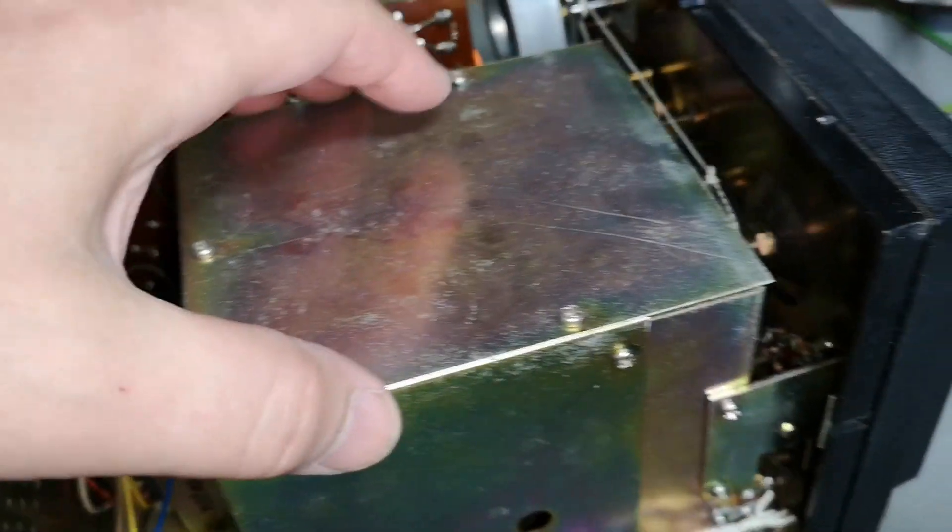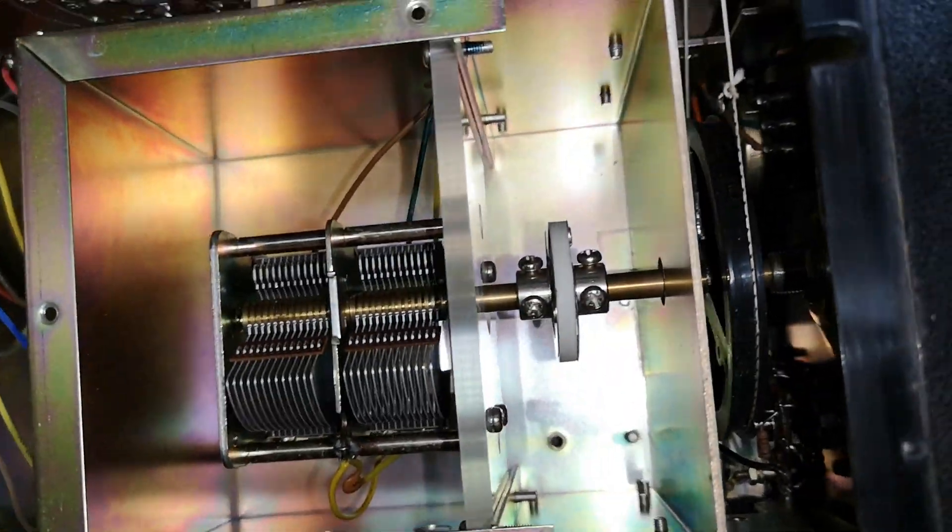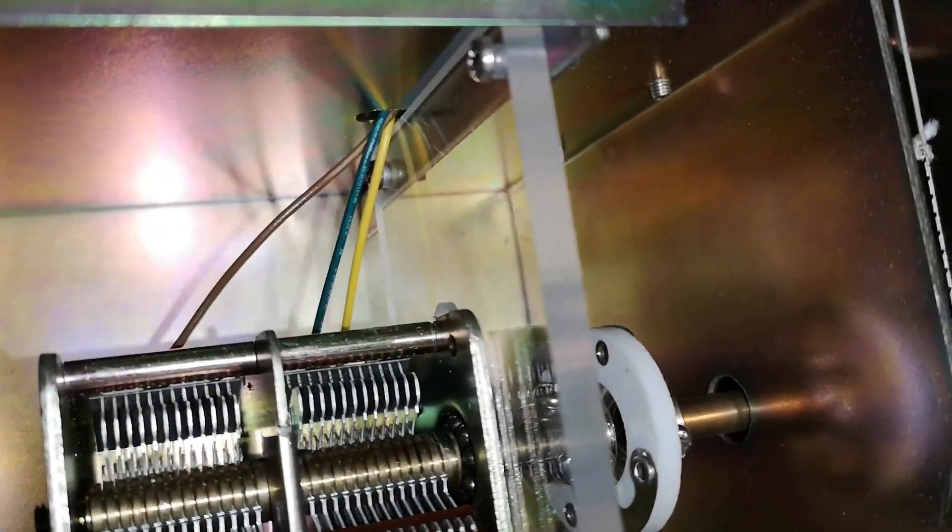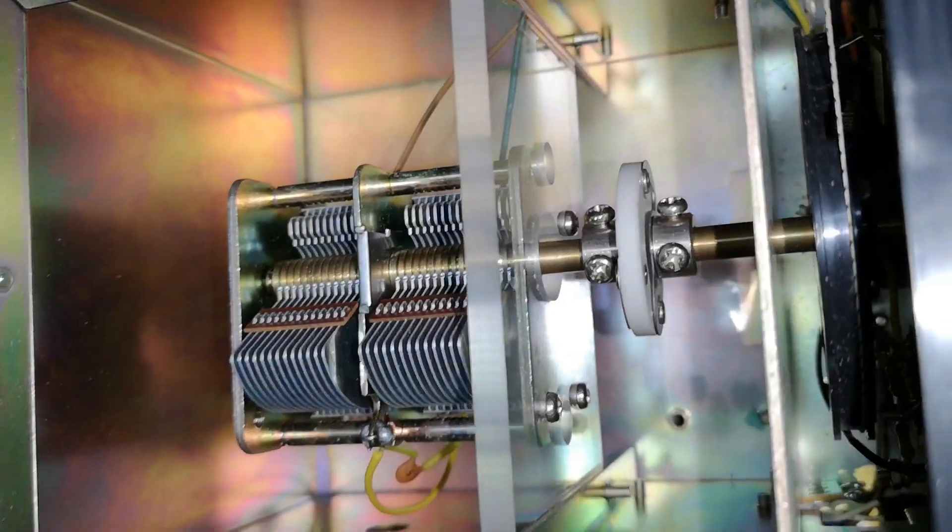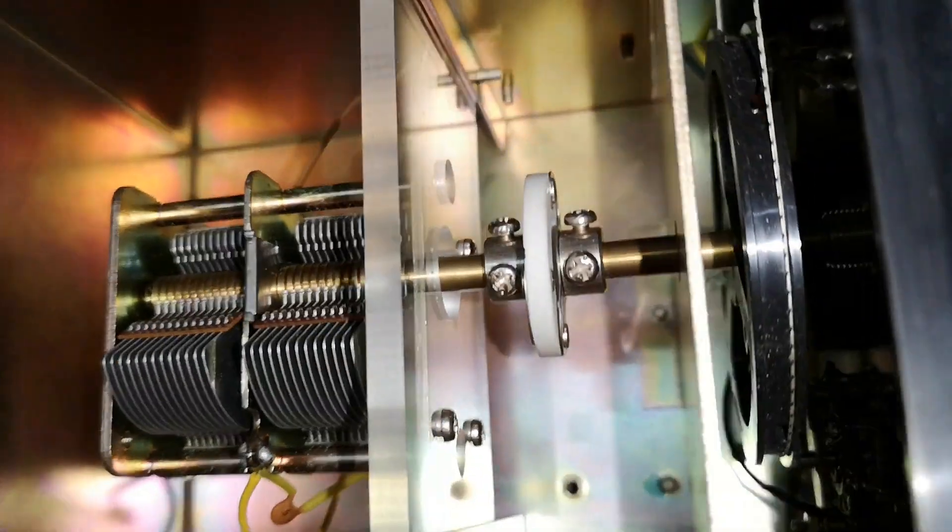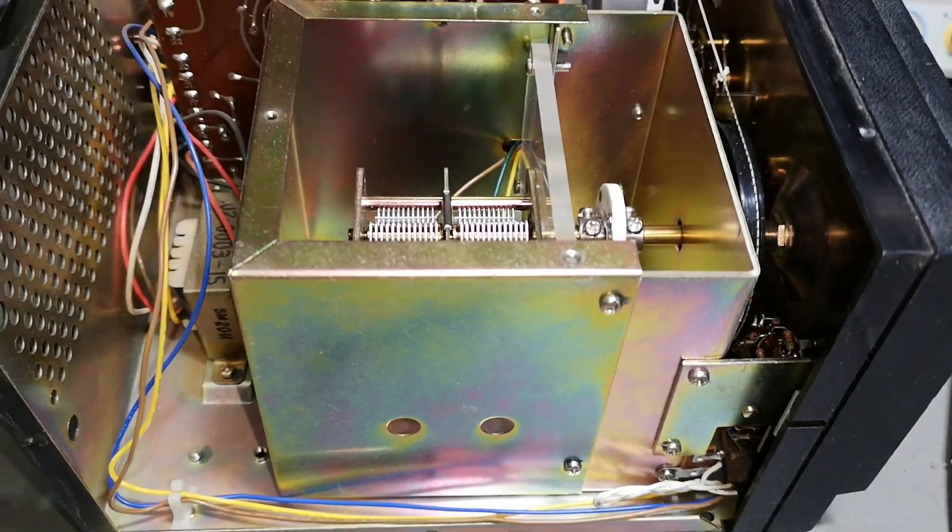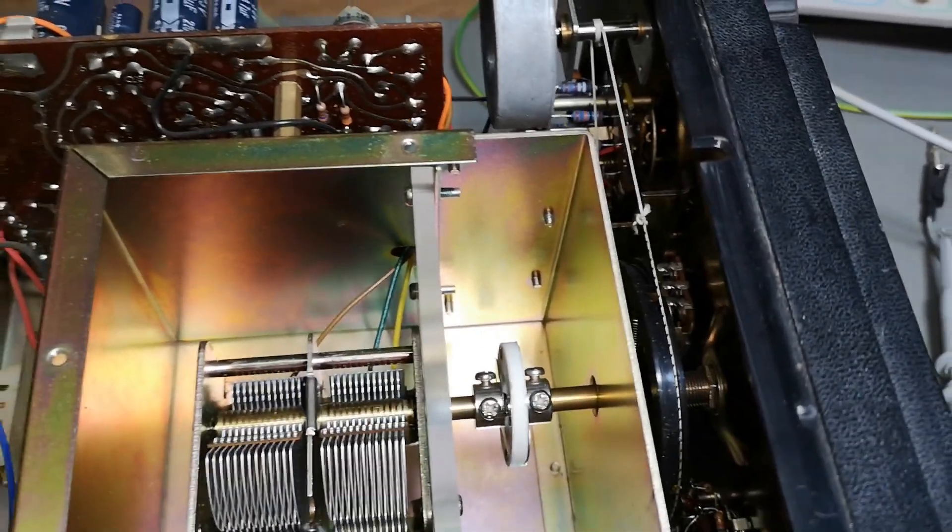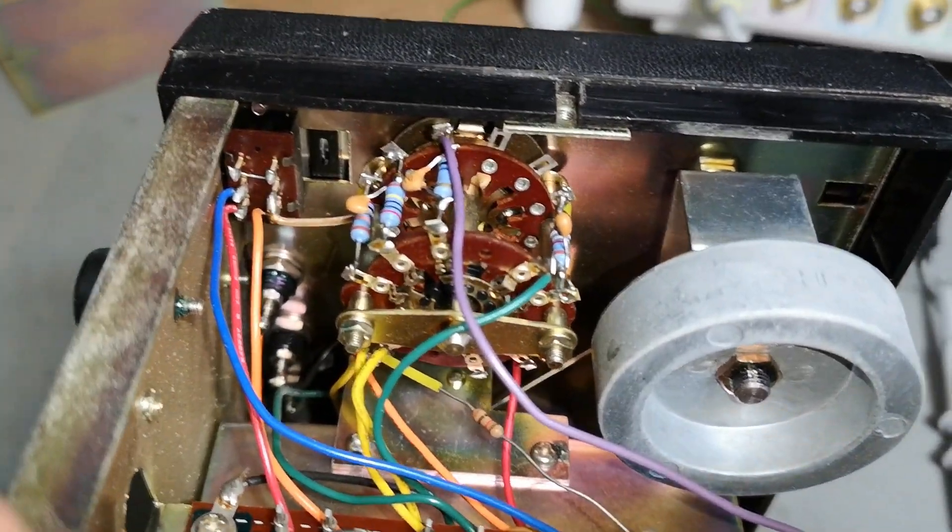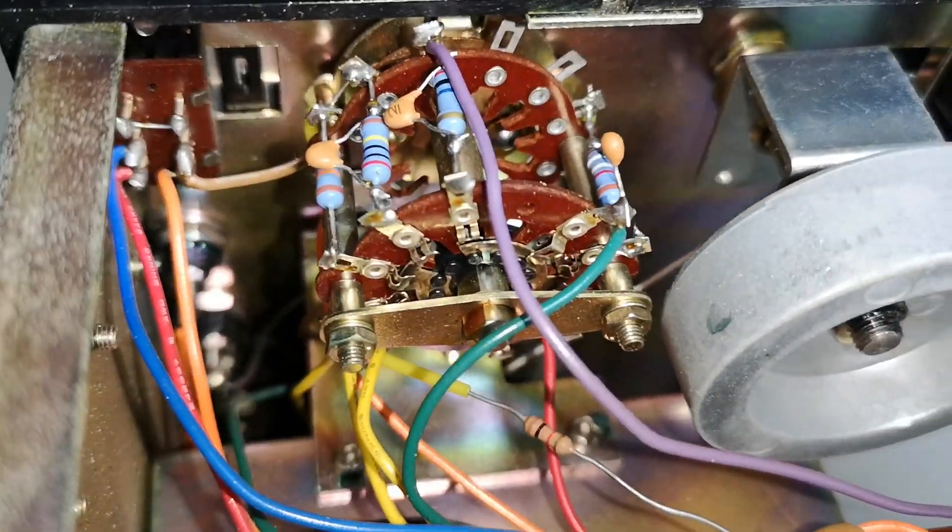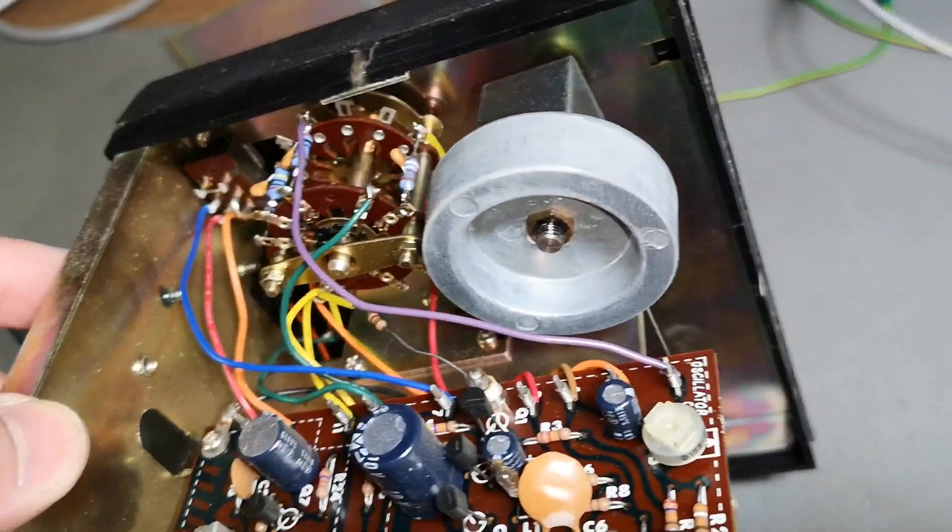I think we have a look inside this, the magic box, the mysterious super cool thingy in here. How do I open this? Only on the top. It's actually really really well made. So here's the capacitor, and the wires used for the capacitors go through that little hole and it's perfectly shielded. It's not even mounted in any metal, it's completely isolated. The shaft is of course isolated as well. And that will be all the range resistors over here. The fun thing is that all the ranges are actually completely right. All I want to do is clean the contacts and then I'll see if everything is good and fine again.